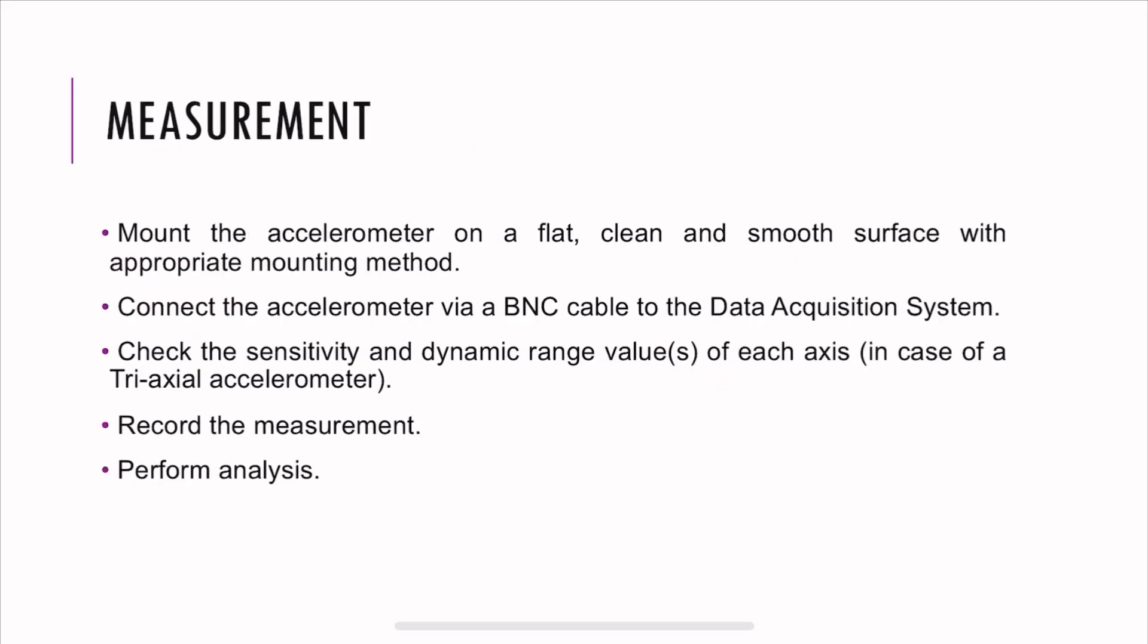How do we measure accelerations? First, you mount the accelerometer on a flat, clean and smooth surface to ensure high degree of transmissibility. Connect the accelerometer via BNC cable to the data acquisition system. Check the sensitivity, dynamic range, all the units, and also for each axis in case of a triaxial accelerometer. Record the measurement and perform the analysis.